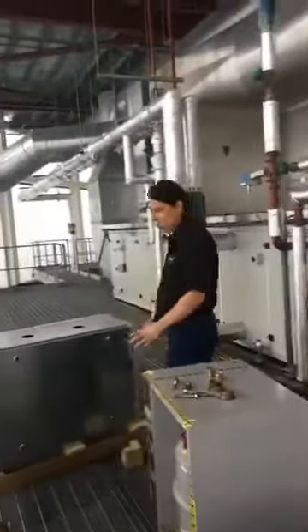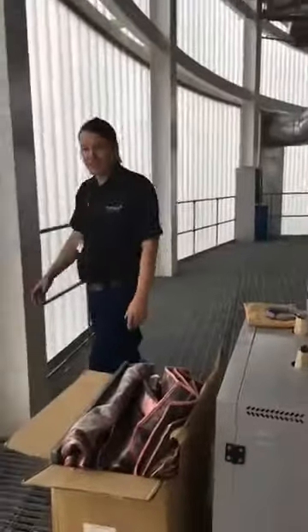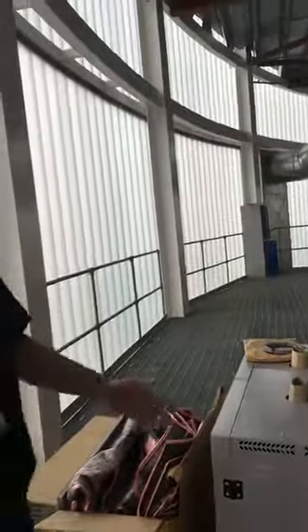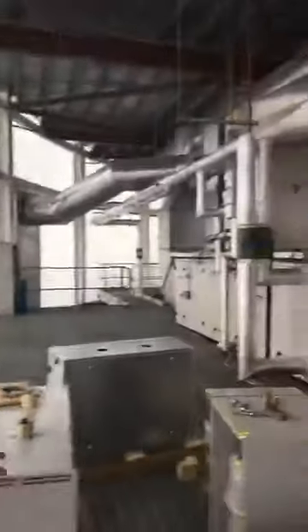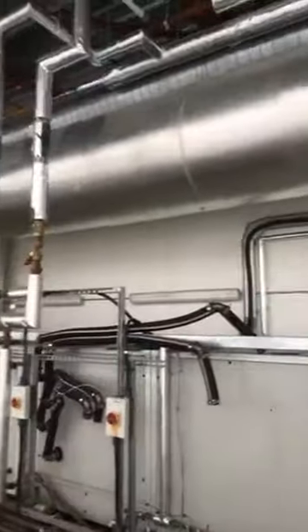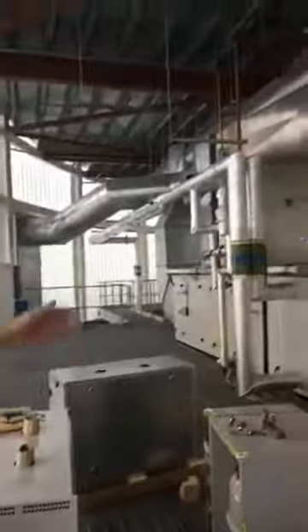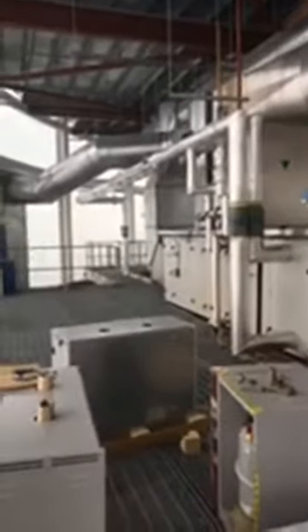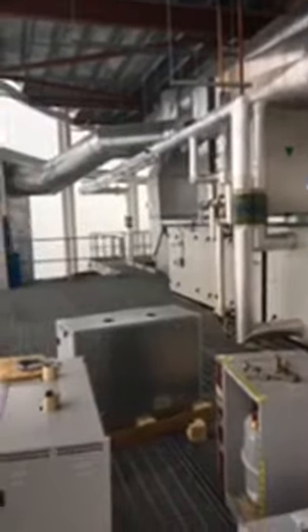So this is quite a small air handler, not actually that big - probably about a third of the size we'd have on the roof. On the roof we'd have something about 3 times as big. It simply works by taking fresh air in from these ducts just over there. It comes in and goes into the first system, which, if it's very cold, would be a frost-stat - basically a radiator or coil that the air goes through, and as it passes through, it picks up the heat.